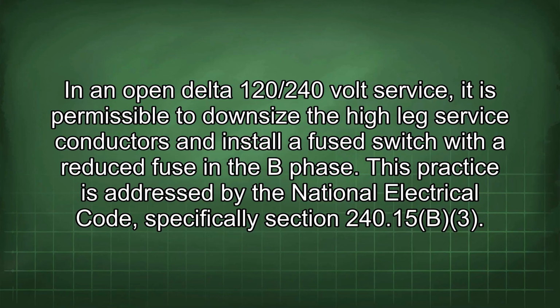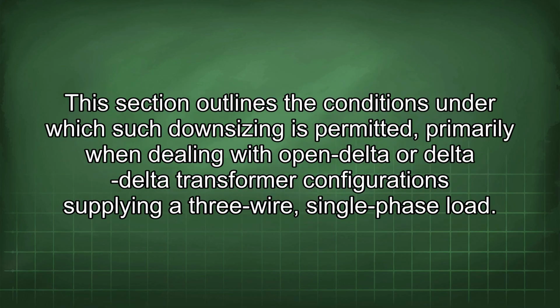In an open delta 120/240 volt service, it is permissible to downsize the high leg service conductors and install a fuse switch with a reduced fuse in the B phase. This practice is addressed by the National Electrical Code, specifically section 240.15(B)(3). This section outlines the conditions under which such downsizing is permitted, primarily when dealing with open delta or delta-delta transformer configurations supplying a 3-wire, single-phase load.